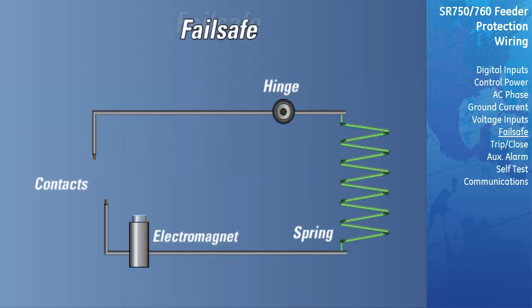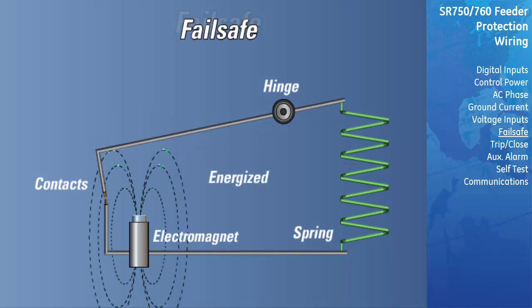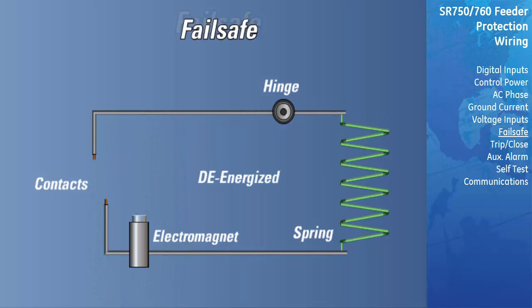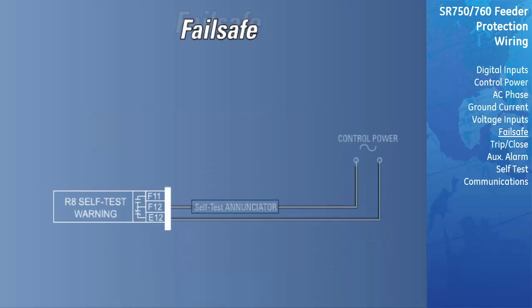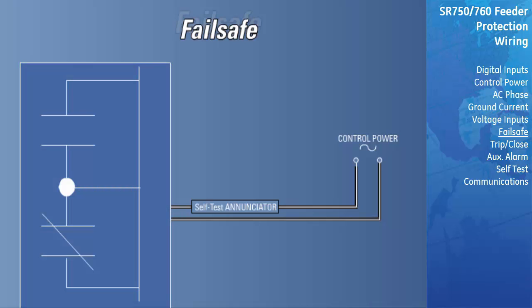At this time, it is appropriate to review the terms failsafe and non-failsafe. GE Multilin defines a failsafe relay as a relay that is normally energized and de-energized when called upon to operate. It will also de-energize when the relay control power is lost. Within the relay, there is only one relay that will always operate as failsafe. This is the R8 self-test relay. It has a Form C contact output configuration and will de-energize if there is a problem with the relay.